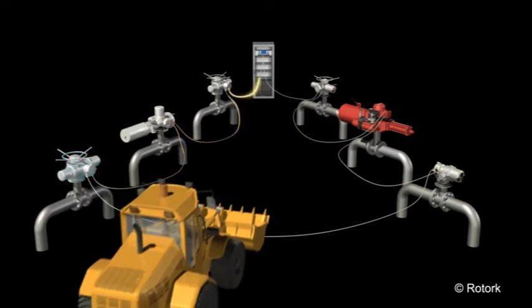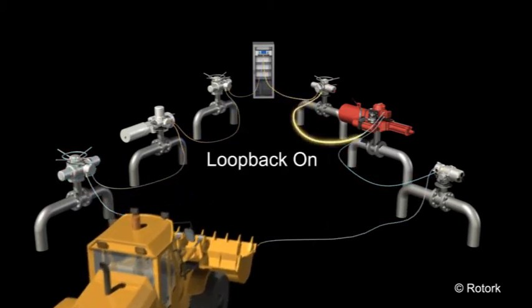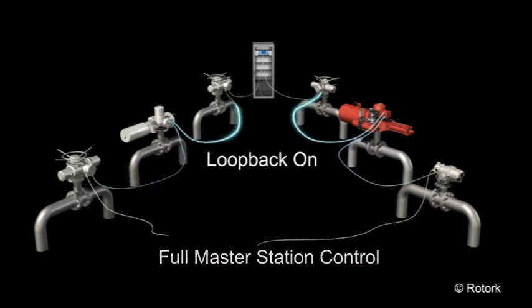In the event of a fault, loop backs are automatically enabled either side of the fault, allowing the master station to maintain full control of all actuators.